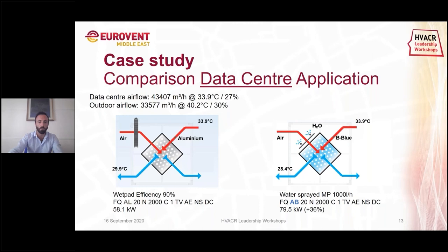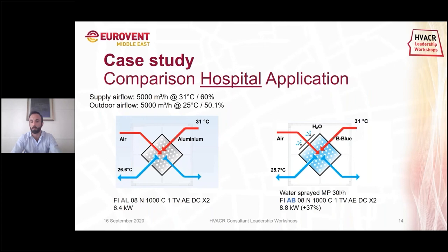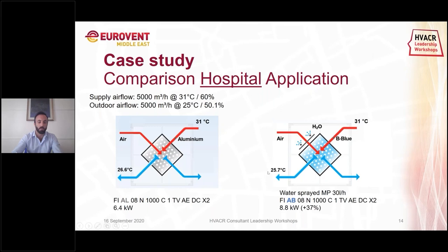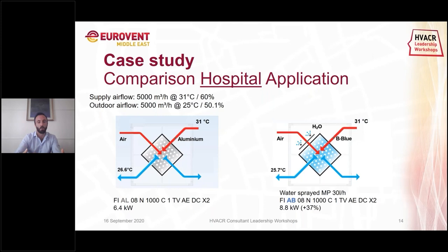Now with the hospital application we see something different. Previously we were wetting the outdoor air; now we are humidifying the extract air, which has relatively stable conditions — around 24–26°C with an almost constant humidity of around 40–60%. In this way we can use the adiabatic humidifier and heat exchanger — the indirect evaporative cooling technology — for the supply air. This technology can really save a lot of energy for running the air handling unit in hot climates, especially when the outdoor air temperature is higher than the indoor temperature.